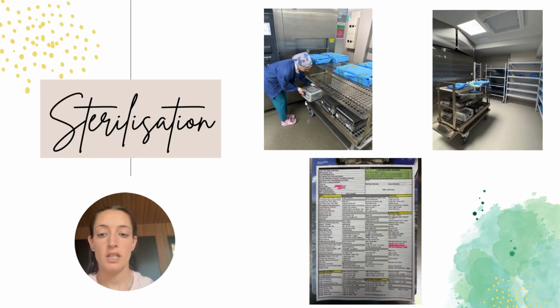I take the steam indicator strip with me and I go back in the clean room where I fill up the sterilization log, circle all the options stating that the cycle passed correctly, and I stick the steam indicator label on it. I take the printout of the sterilizer, circle the correct load, check that the sterilization lasts for at least 4 minutes, as our sterilizer has been programmed for 4 minutes, and sign the printout, and then I attach it to the sterilization log.